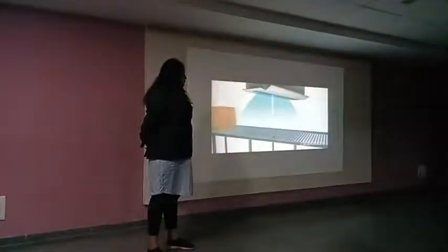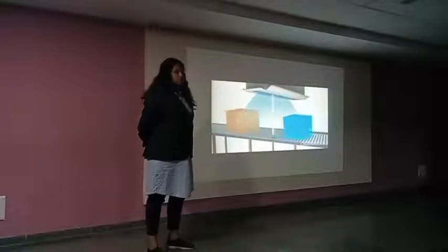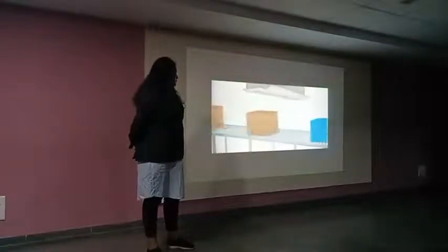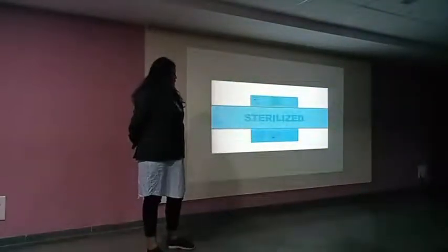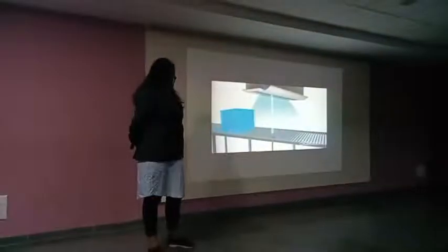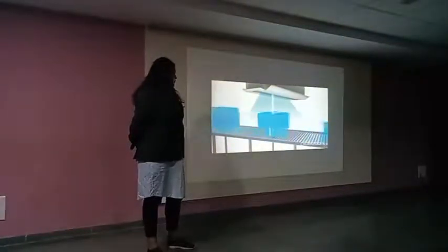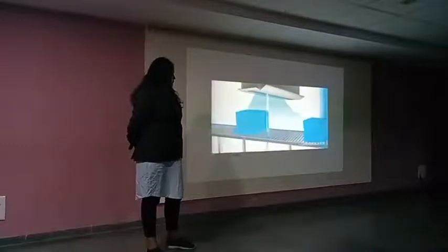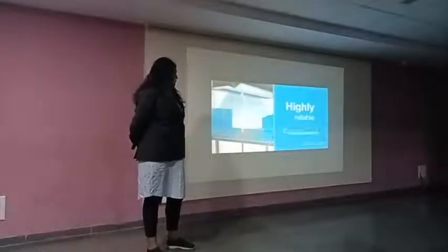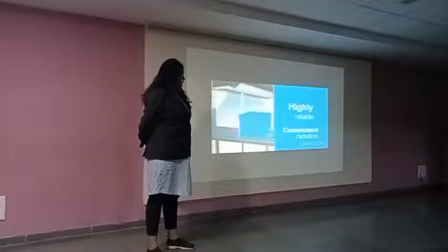Boxes of medical devices are put on a conveyor in a single layer, and as they pass through the beam, the electrons penetrate the cardboard box and all the medical devices in their individual packages inside the carton. Harmful microorganisms are completely inactivated with minimal effect on the medical devices. As the electrons penetrate the products, the radiation dose diminishes, so less radiation leaves the box than entered. Medical devices are usually turned over and irradiated from the opposite side in order to get a relatively uniform dose. Electron beam machines are highly reliable and provide consistent radiation sterilization because the dosing they provide is precisely repeatable.